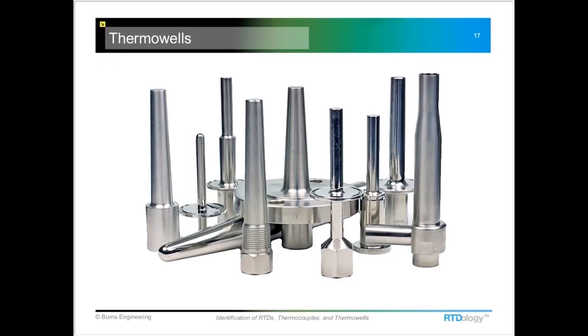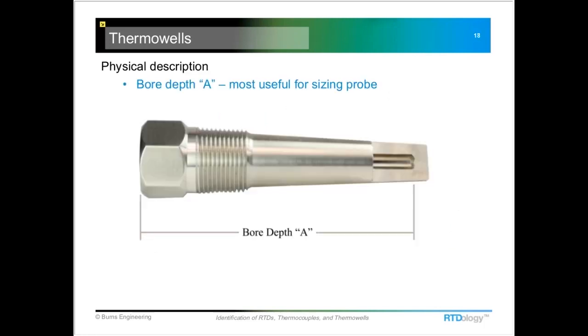Next I want to talk about thermowells. If you have a thermowell and you need a replacement probe to go in it, the most important useful number is the bore depth. This can be measured quite easily by just taking a piece of wire or even the probe that comes out of that well.